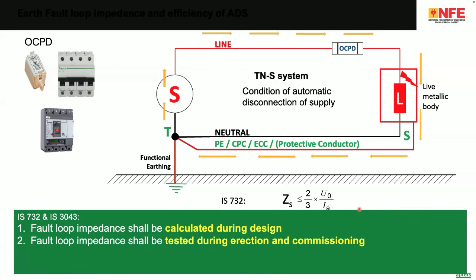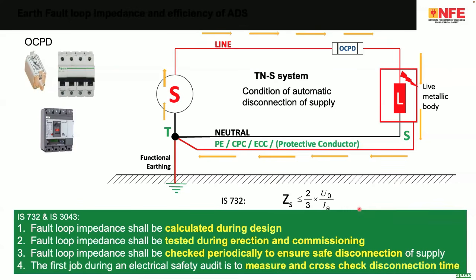This subject has to be calculated during design. This has to be tested during erection and commissioning. This has to be checked periodically to ensure safe disconnection of supply. And this is one of the first electrical safety measures when you do a safety audit. Keep this in mind. The subject is earth fault loop impedance.